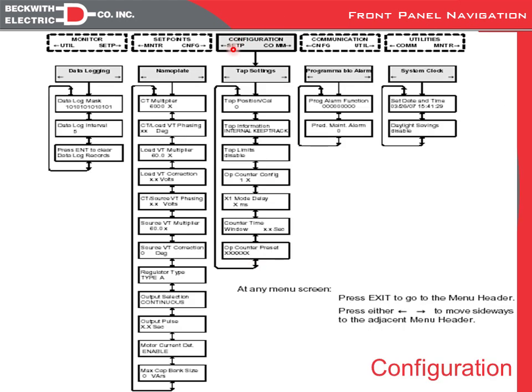And here's another set of screens, and this would be for configuration. Now, anything in set points is set off a level 1 password. Anything under configuration is going to require a level 2 password to change. So here's another way I can change the tap position. And again, we can go through, and once you get into one of these loops, if you keep hitting the down arrow button, you'll come back to the top again. So for instance, if I started here, and this is the setting I wanted to change, if I come down to this one, then hit the up arrow button, it'll actually bring me back around, and I can get to this guy with only 2 keystrokes. So instead of hitting the down arrow button several times from the top of the screen, if you hit the up arrow, it'll loop you back to the bottom of the screen and vice versa.